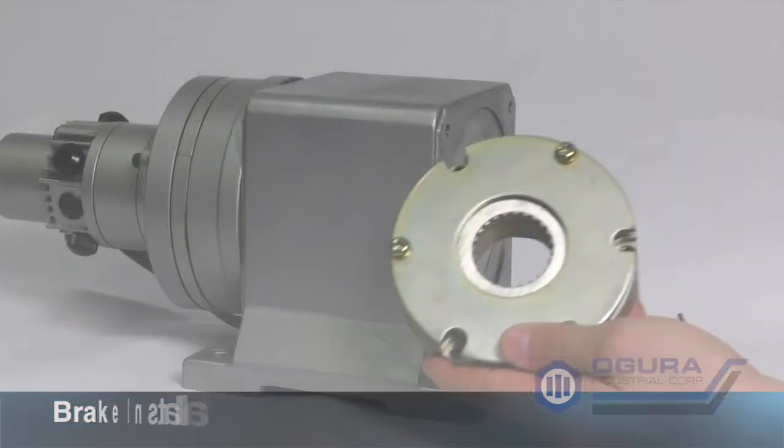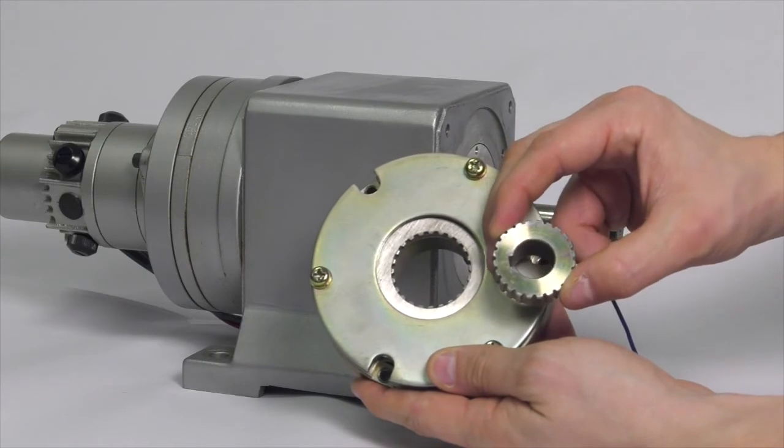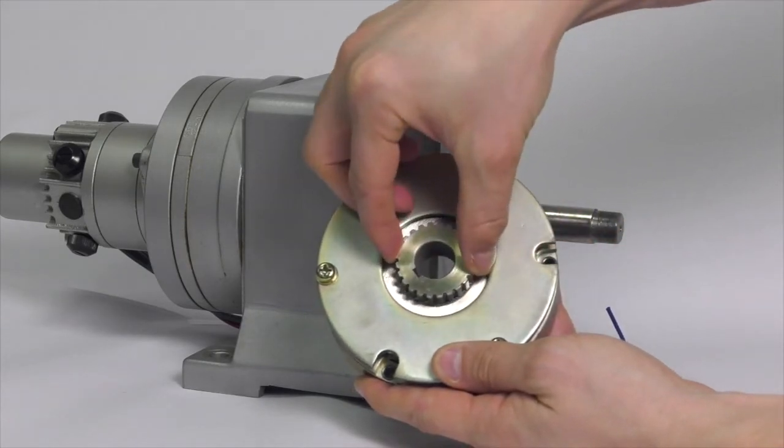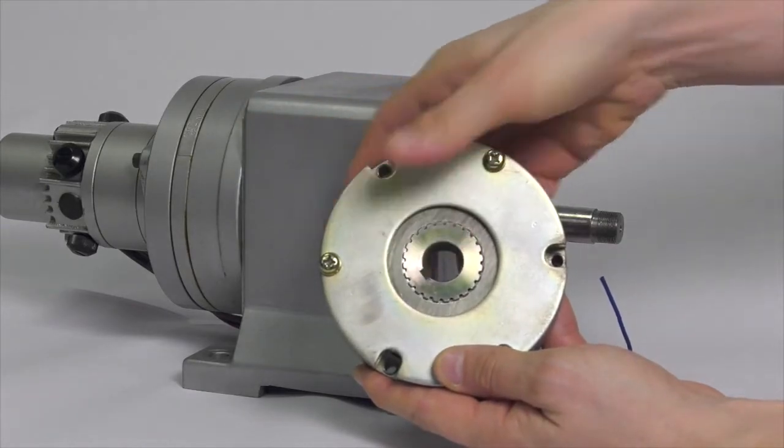For smaller spring applied brakes, insert the hub into the brake and then temporarily connect the leads to your power supply, making sure the connections are properly insulated. The voltage going to the brake should be at the rated voltage shown on the label.